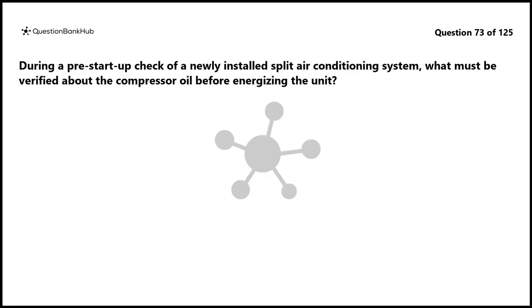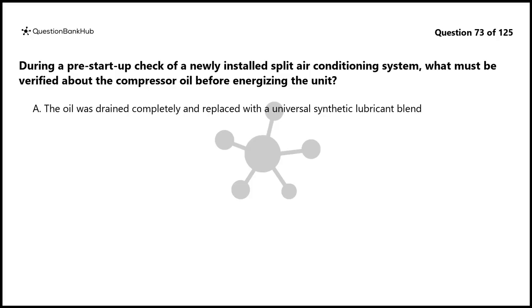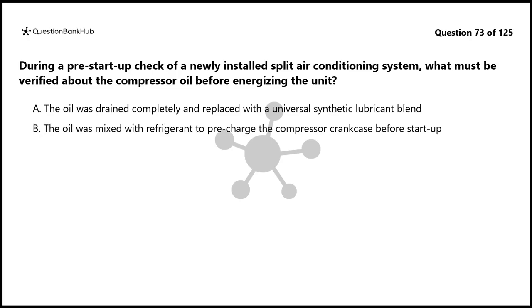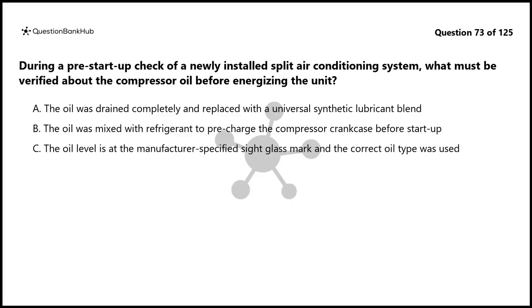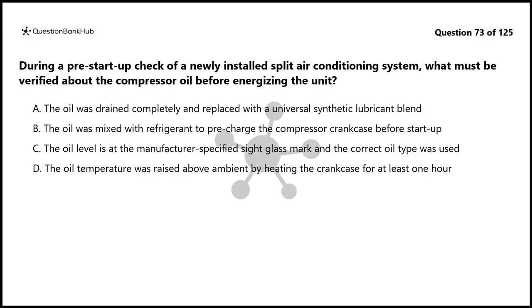Question 73. During a pre-startup check of a newly installed split air conditioning system, what must be verified about the compressor oil before energizing the unit? A. The oil was drained completely and replaced with a universal synthetic lubricant blend. B. The oil was mixed with refrigerant to pre-charge the compressor crankcase before startup. C. The oil level is at the manufacturer's specified sight glass mark and the correct oil type was used. D. The oil temperature was raised above ambient by heating the crankcase for at least 1 hour.